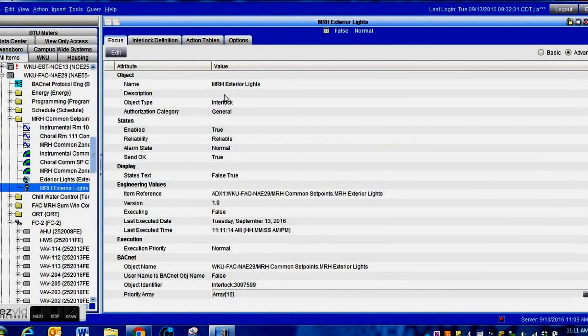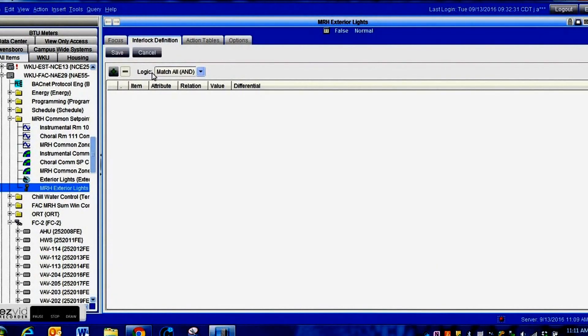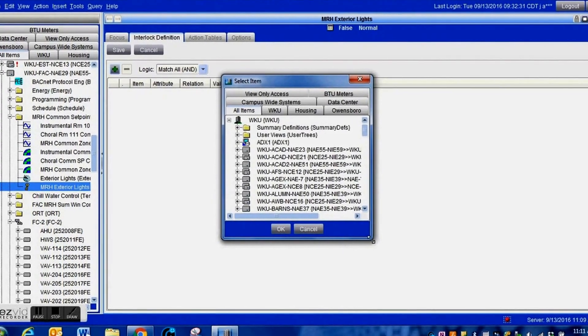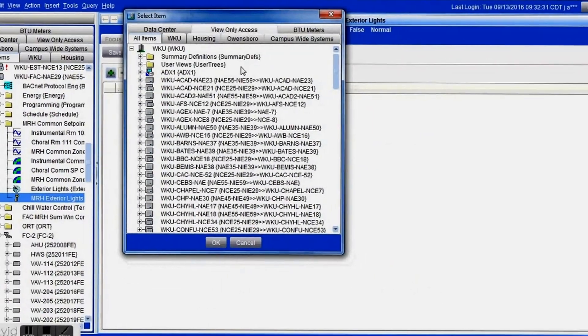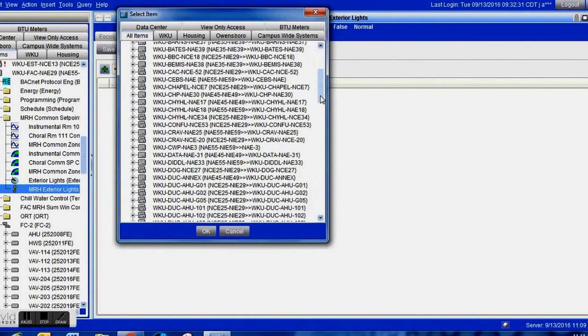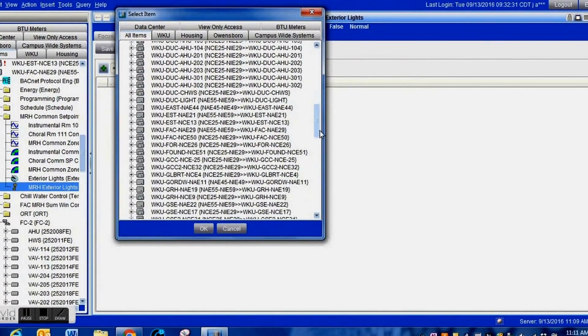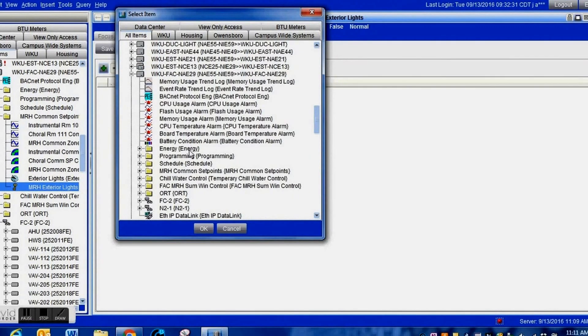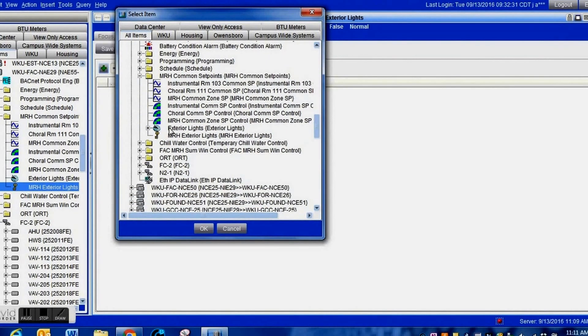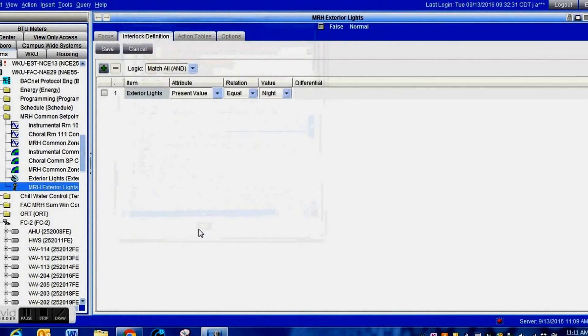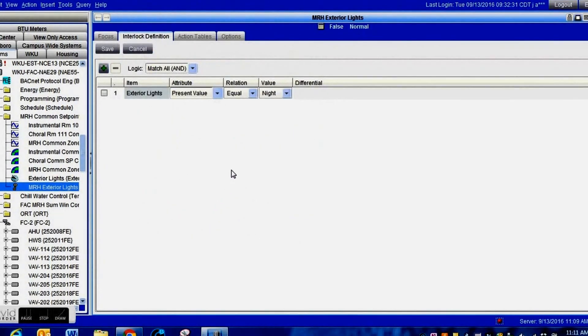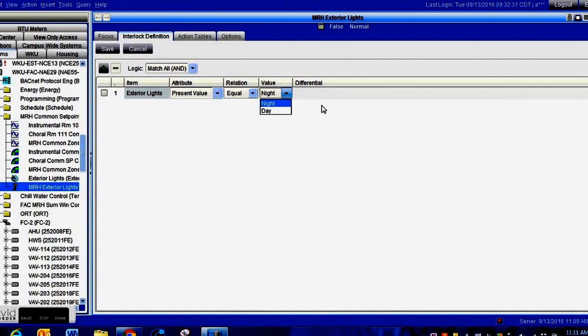Now that we have our interlock setup, we're going to go into the interlock definitions. This is where our question is asked. We're going to hit the plus sign and drill down through our network to find the solar clock we just created. That is how we will link it to this interlock. I'm going down into my controller, dropping down the folder, there is the solar clock we created. Highlight it and press OK.